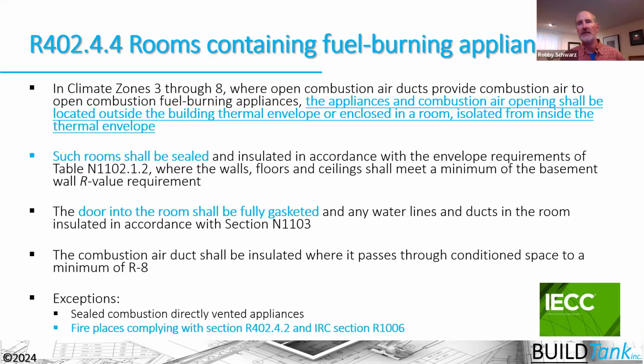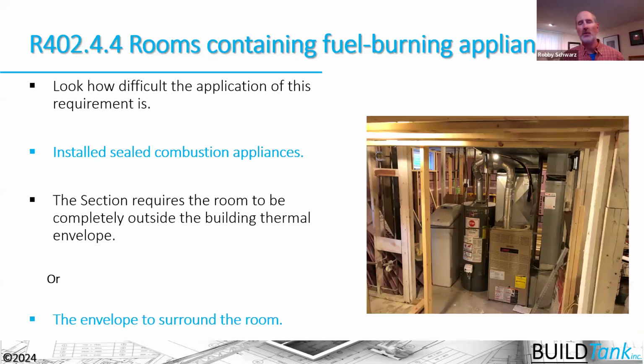But if I have a forced air system, or I have a gas burning boiler, or an atmospherically vented water heater, for example, I have to bring in combustion air for those appliances. And therefore, I have to build an airtight, air sealed, insulated building thermal envelope around that mechanical room that separates the mechanical room from the conditioned space of the house, so that that combustion air doesn't impact the comfort and efficiency of that house and or the loads of that house. And you can see that when that mechanical room is within the building thermal envelope, maybe the center of a basement or something like that, it's very, very difficult to separate it from the rest of the house.